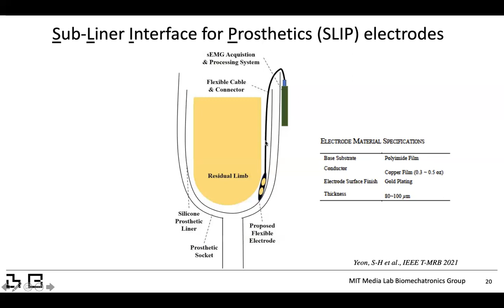The electrodes themselves are very flexible, and they have a long cable that comes out and attaches to an embedded electronic wearable surface EMG acquisition and processing system. They're made out of Kapton, which is a polyimide polymer film that's only about 100 micrometers thick, and they're gold-plated copper film underneath this insulating substrate. That's the concept of them, and this is how they actually look.